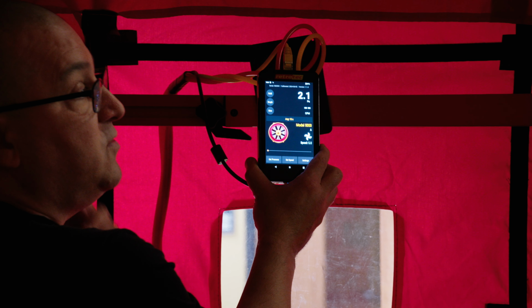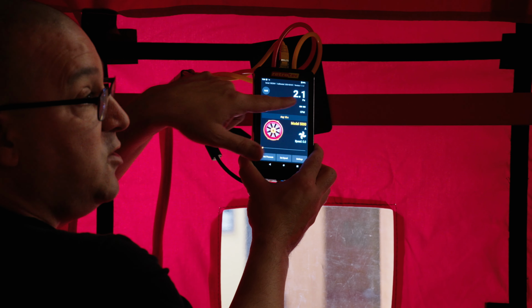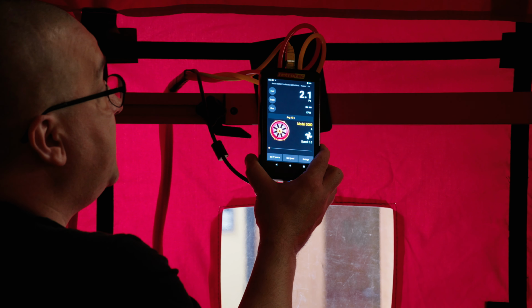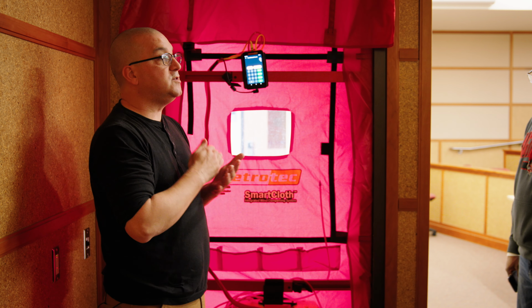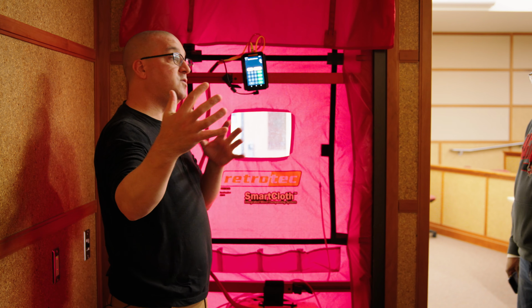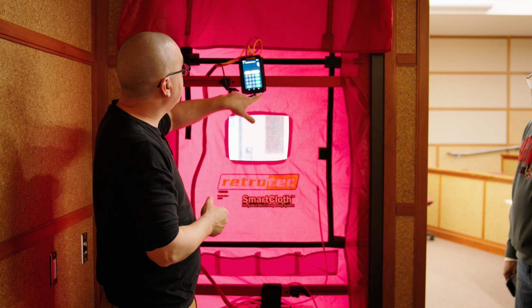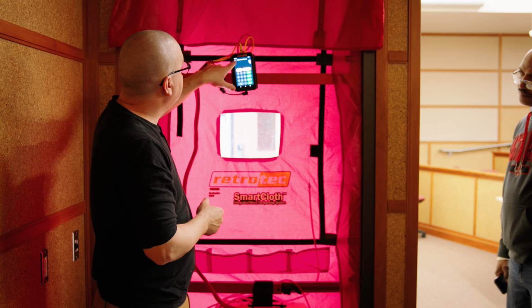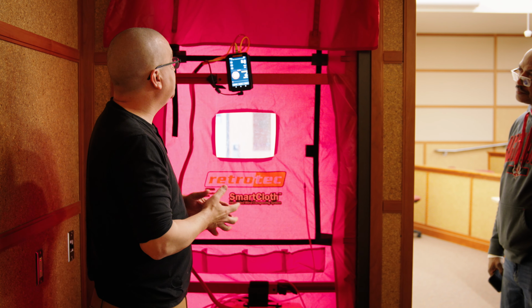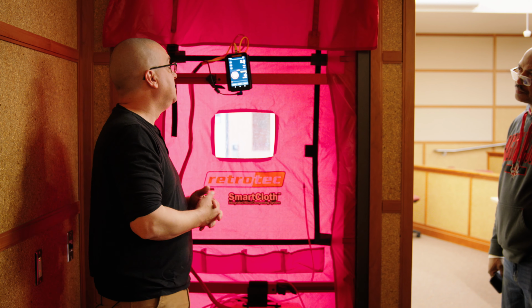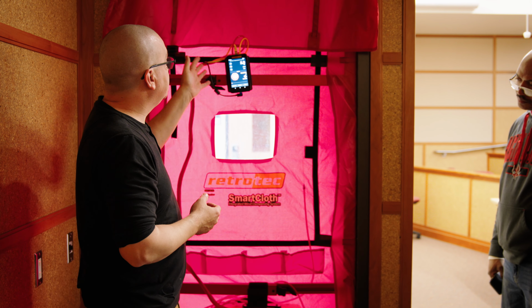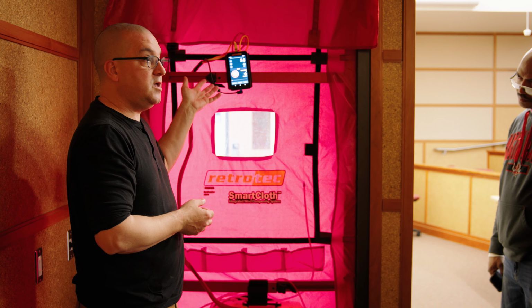So when somebody asks, what's the blower door number? It's the cubic feet per minute, the CFM number here. 50 pascals is the standard pressure, that 20-mile-per-hour wind hitting the house. So I set this, get it up to speed, and then I can read what the CFM is here. This is the newest Retrotec gauge.